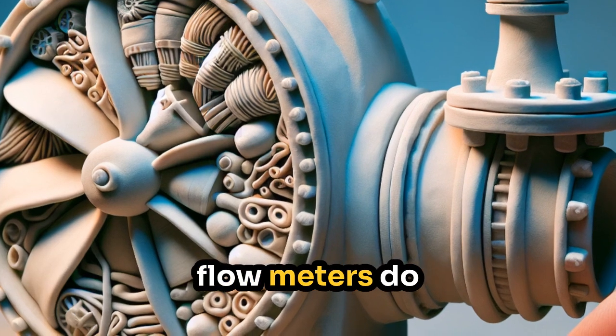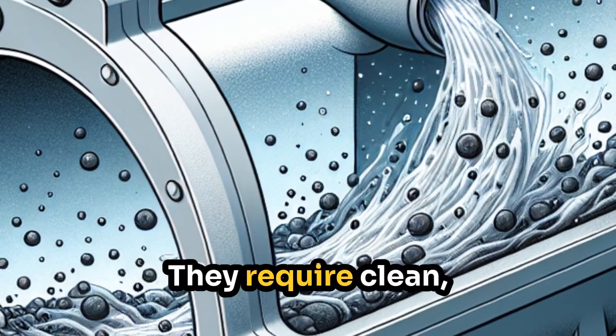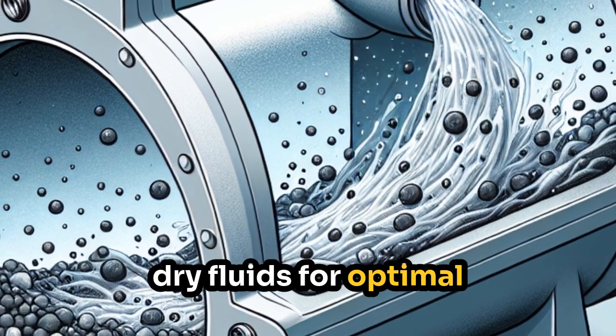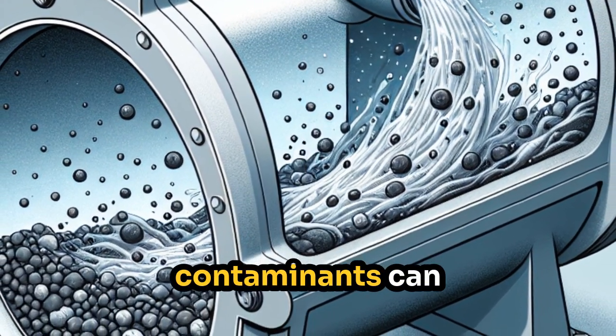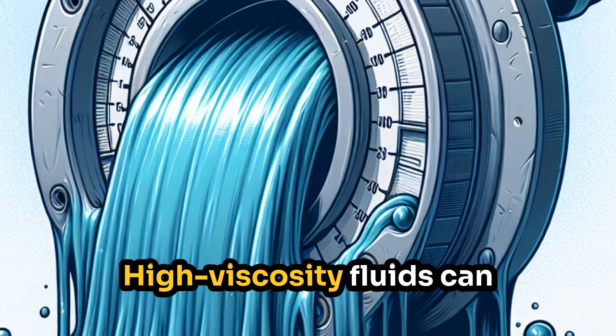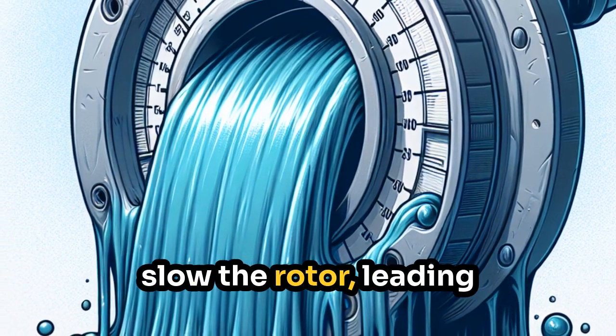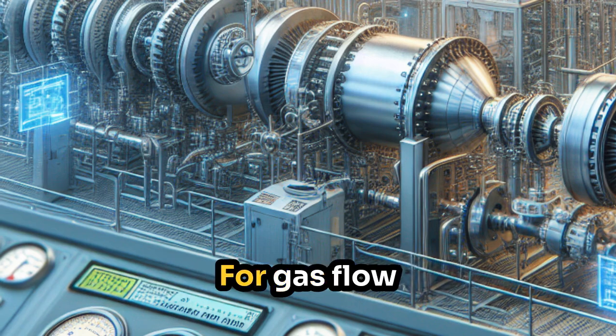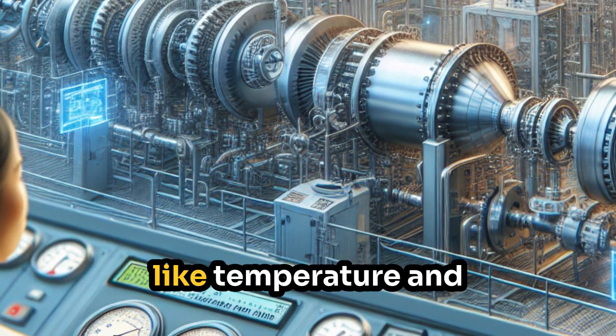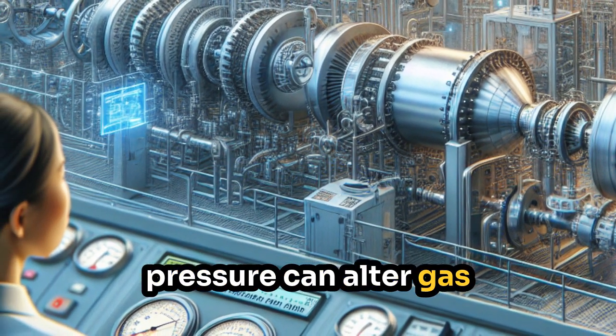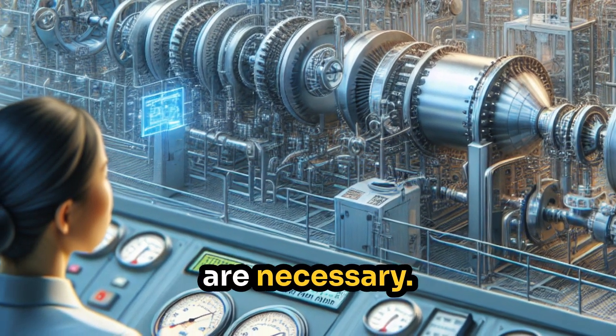However, turbine flow meters do have limitations. They require clean, dry fluids for optimal performance, as contaminants can damage internal components. High-viscosity fluids can slow the rotor, leading to inaccurate readings. For gas flow measurement, factors like temperature and pressure can alter gas density, so corrections are necessary.